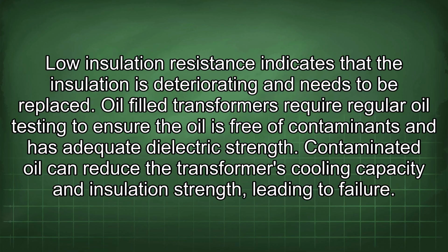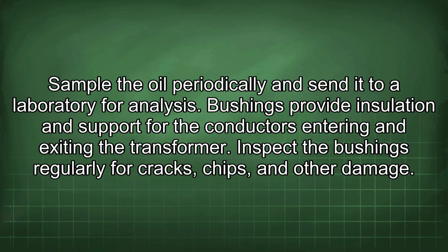Oil-filled transformers require regular oil testing to ensure the oil is free of contaminants and has adequate dielectric strength. Contaminated oil can reduce the transformer's cooling capacity and insulation strength, leading to failure. Sample the oil periodically and send it to a laboratory for analysis.